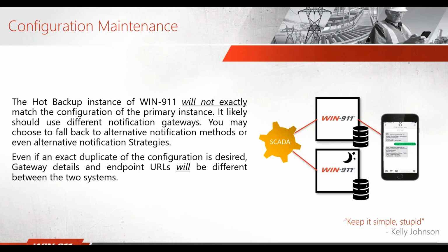own hardware. In fact, you could have your primary system use one notification method, and your secondary system doesn't have to match exactly. It could be using a totally different notification type. So maybe your primary uses voice calls and it calls your operators. You can have your secondary system or your hot backup send text messages or send emails or use the mobile app. So the configurations of these two systems don't have to be the same.